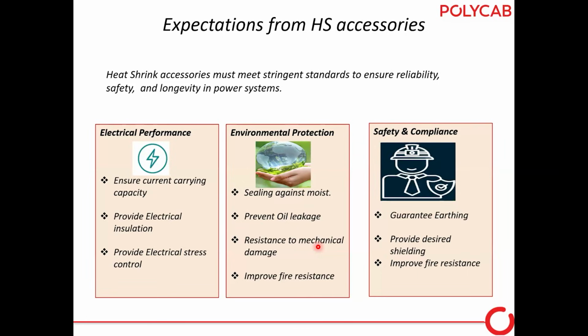Heat shrink accessories must meet stringent standards to ensure reliability, safety, and longevity in the power system. Three parameters are always there whenever any customer or user chooses cable accessories: electrical performance, environmental protection, and safety and compliance. In electrical performance, it should ensure current carrying capacity as per the cables. So if the cables are 300 square mm, 11 kV, the cable joints or terminations should be the same kind. It should provide electrical insulation, or provide electrical stress control. We will see what electrical stresses there are in detail in the coming slide.